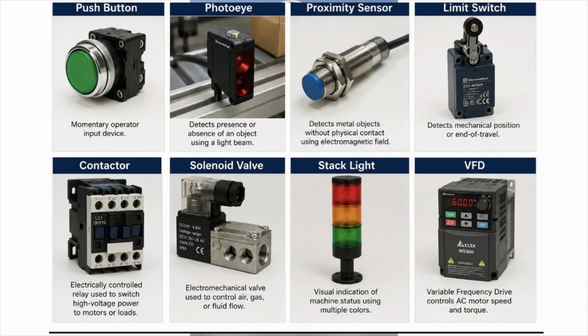Let's talk real hardware you'll actually touch. Typical inputs: push buttons, photo eyes, proximity sensors, and limit switches. These are how the outside world talks to the PLC. Typical outputs: contactors, solenoid valves, indicator lights, VFDs, variable frequency drives, and buzzers or alarms. These are how the PLC talks back to the outside world.